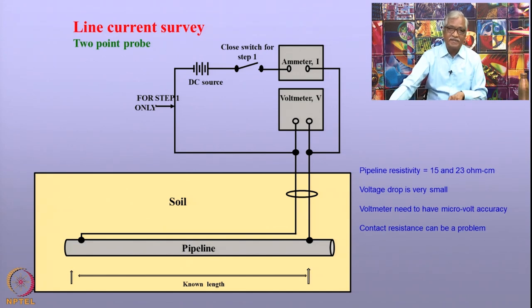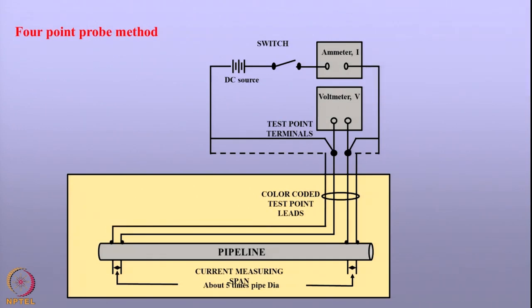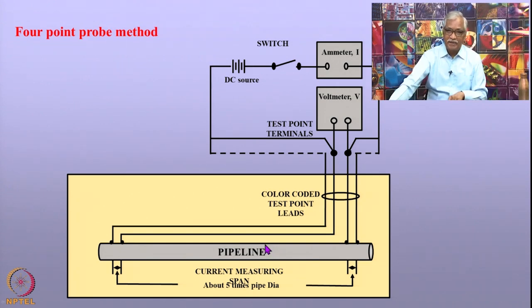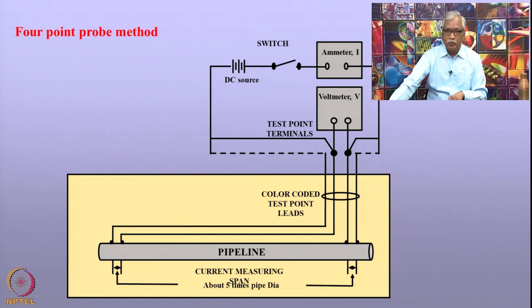In order to overcome this, a four-probe technique is used. In the four-probe technique we have four probes: through the external probes a known current is passed, and through the internal probes the potential is measured. Since we know the current and the voltage, the resistance of the pipeline is measured accurately. In this case, there is no need to know the resistivity of the pipeline, so this technique is advantageous compared to the two-point probe method.